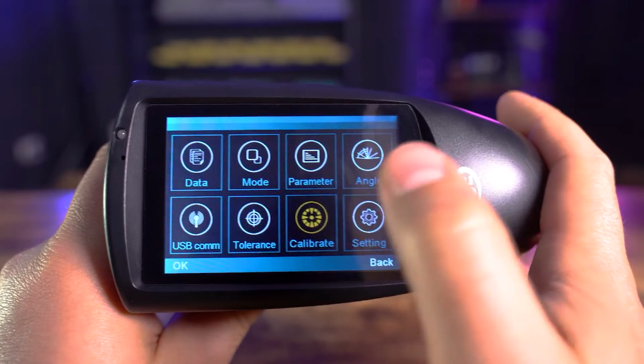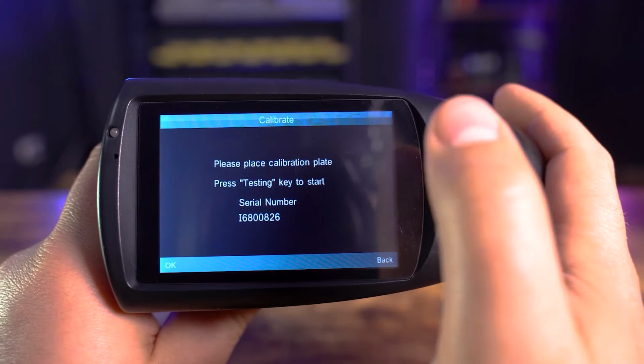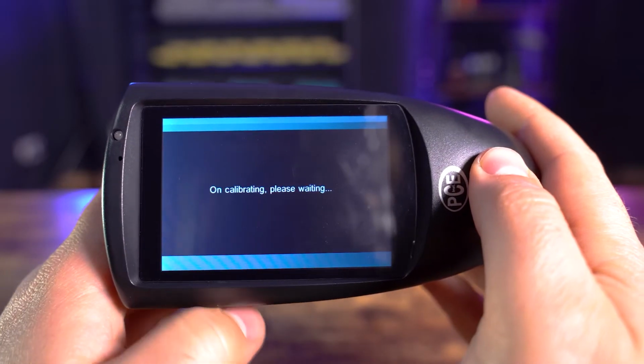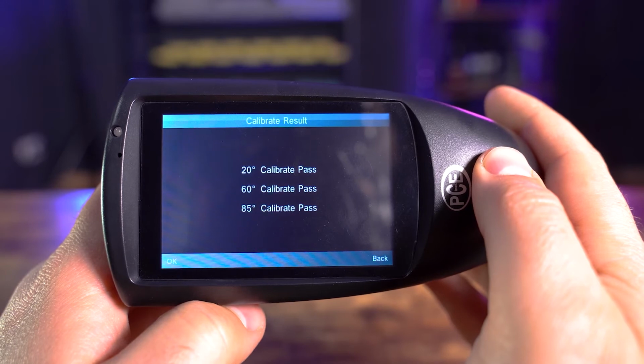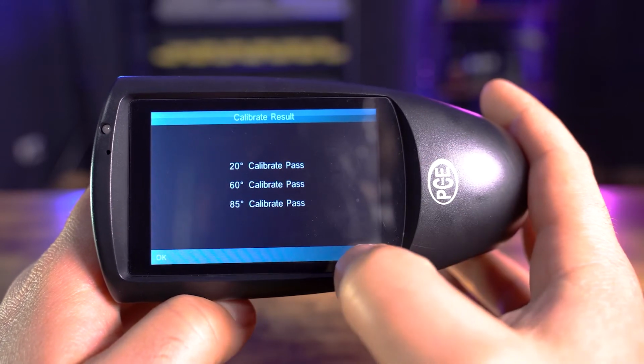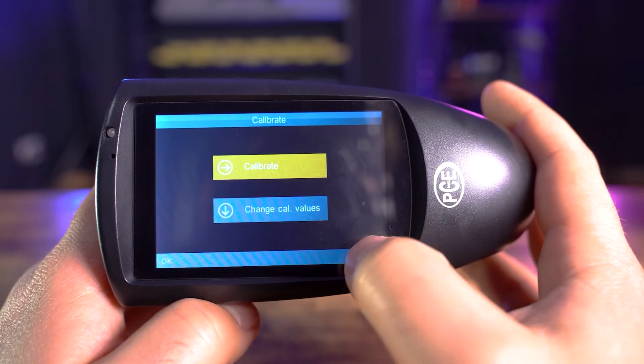One menu point further we find the calibration settings. During the calibration, the safety cover has to stay on the device. So the calibration plate is properly fixed, and the calibration can be done without problems. With the signal calibration pass, we know that all is calibrated.